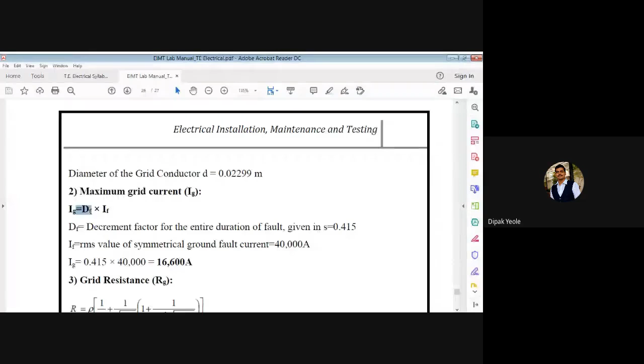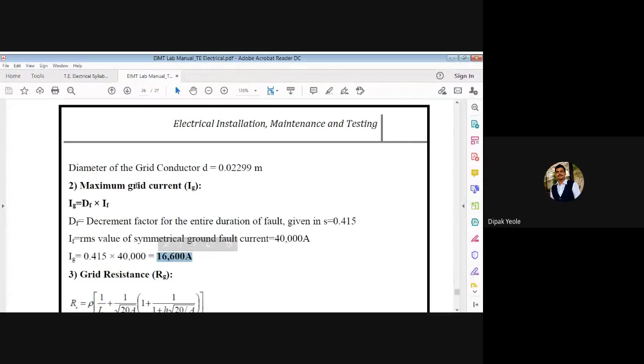Df is a decrement factor, which they have given as 0.415. They have given the RMS value, which is the maximum value, 40,000. We have to take this product and we will get the maximum grid current as 16,600. You have to remember that this grid current is an essential parameter for designing the earthing system.